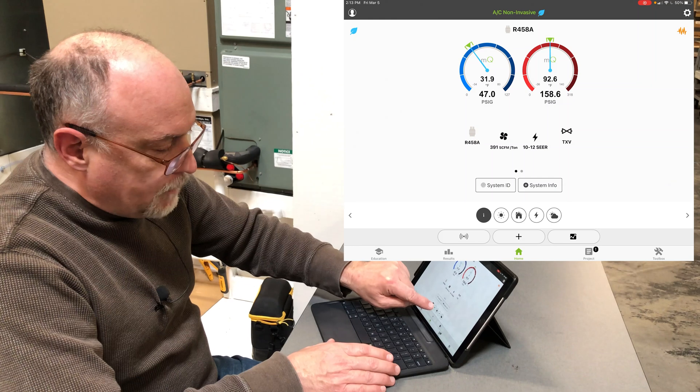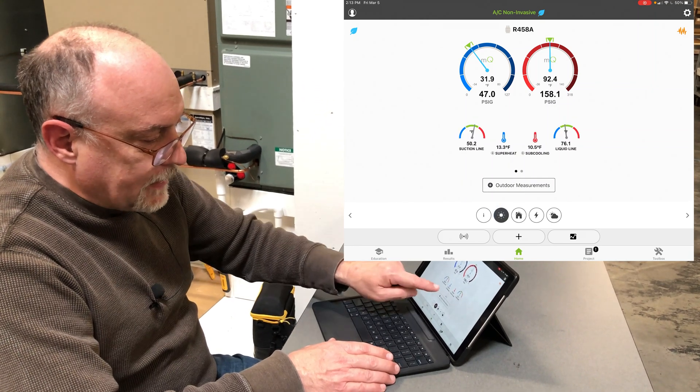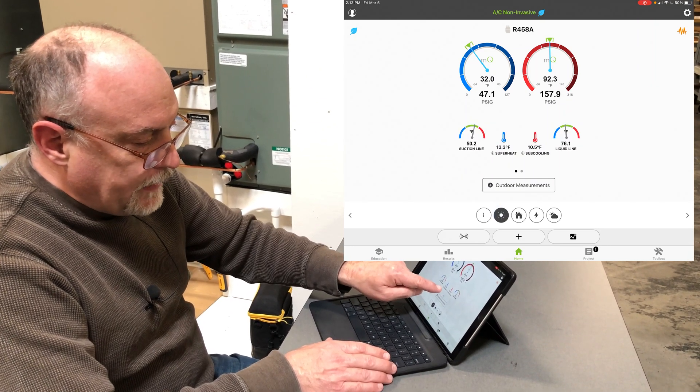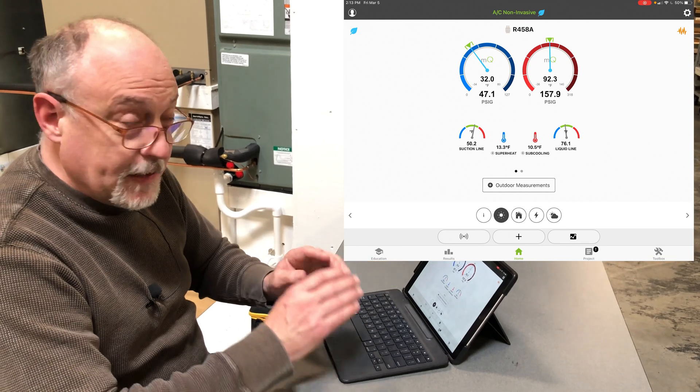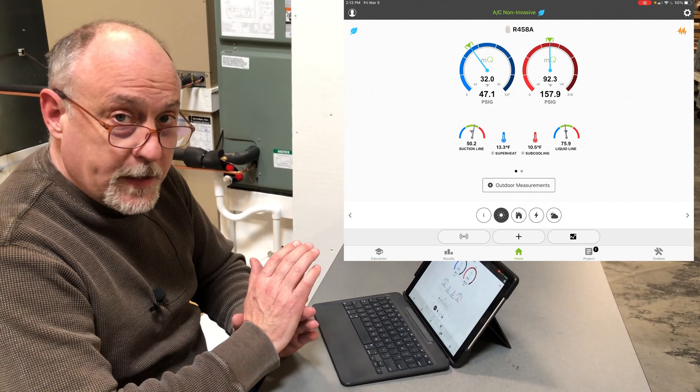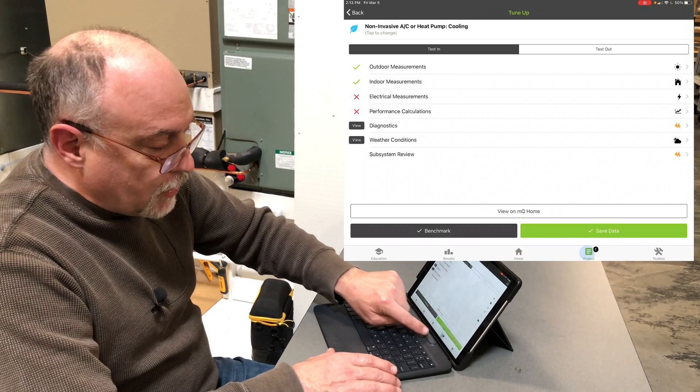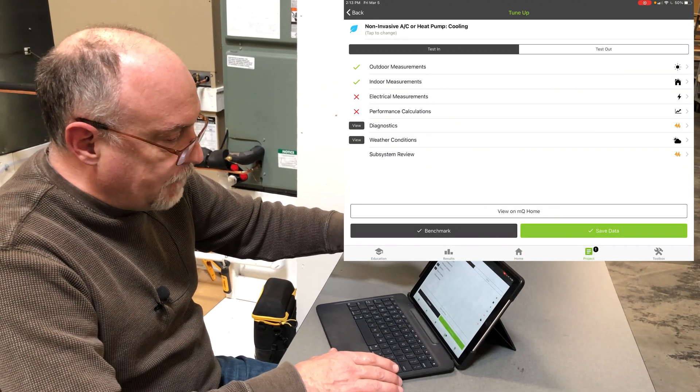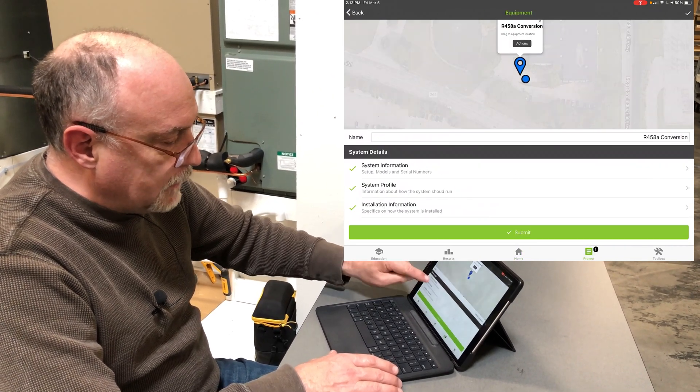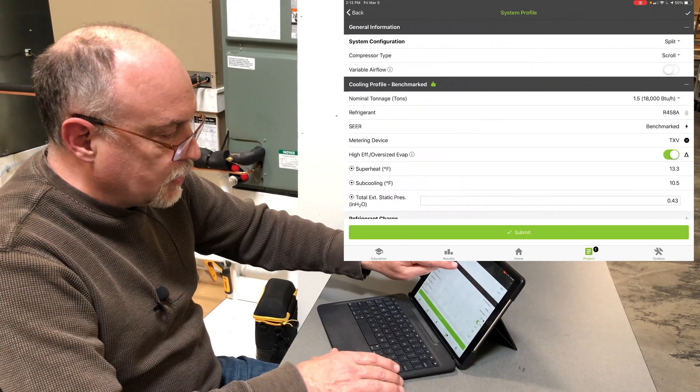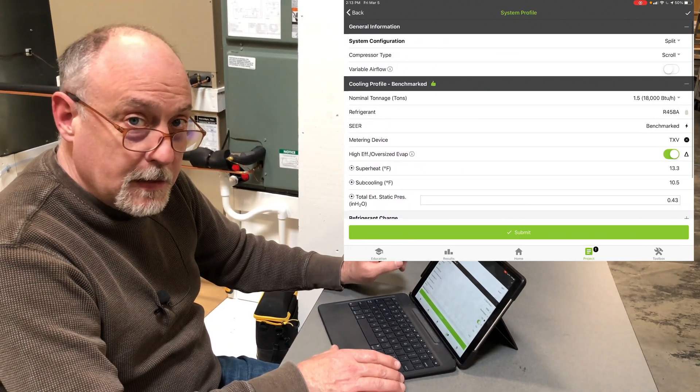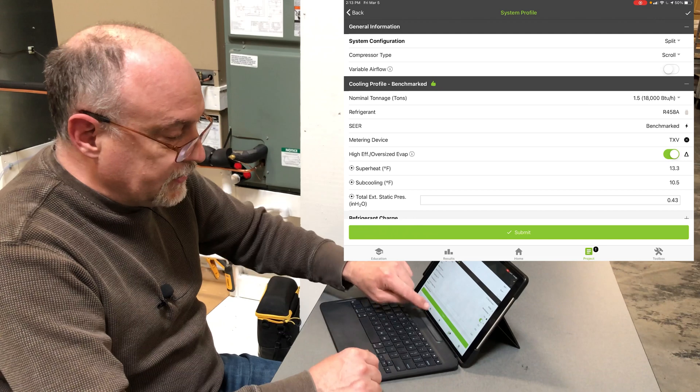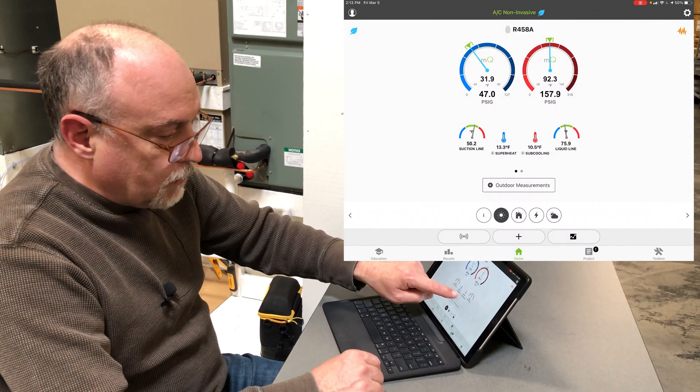If I go to my superheat and subcooling targets, you'll see there's a superheat of 13.3 and a subcooling of 10.5. Those are the targets that MeasureQuick is looking for, and those are from the benchmark. If I go to the project and back to the system profile itself, you'll see the cooling profile is benchmarked at the top, because when I started this up, I benchmarked the system.